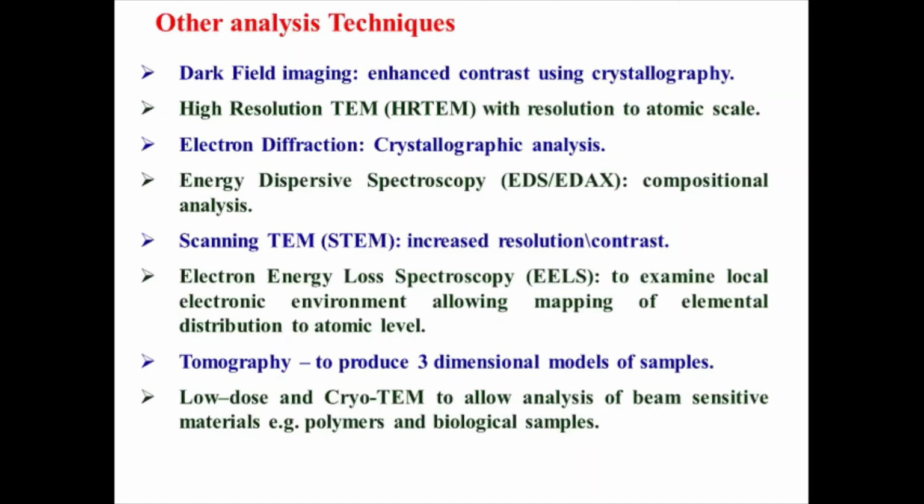But for EELS, you require very sophisticated energy spectrometers, and the cost is very huge. It goes in crores. So very rarely you get a TEM with EELS attachment unless it's a very good institute doing surface science studies or basic studies. So they have the TEM with EELS. Otherwise, you have to get only TEM as a standalone.